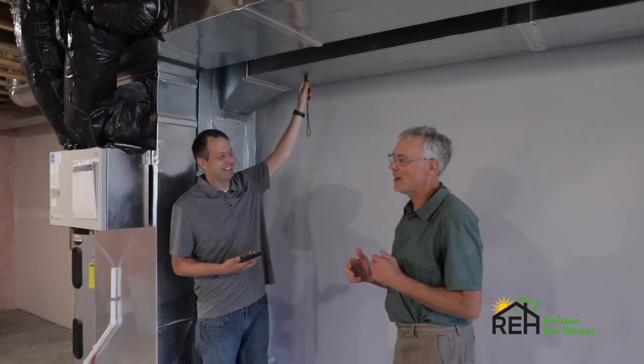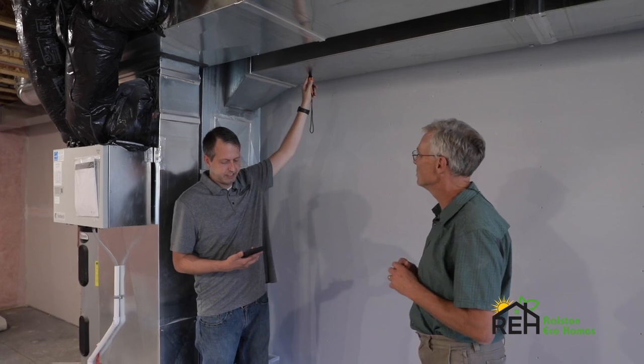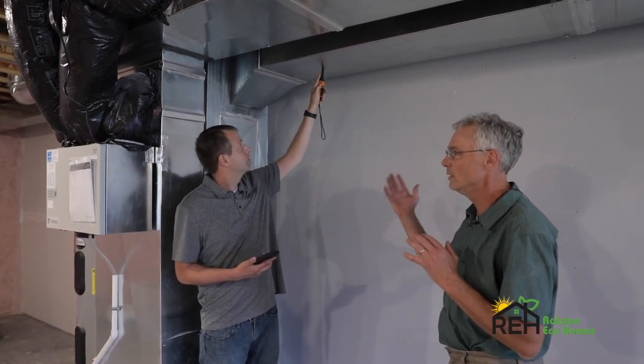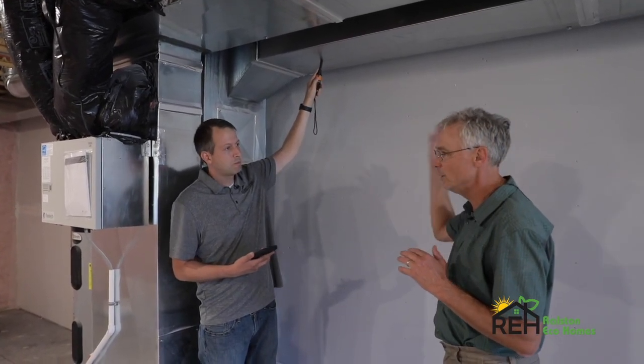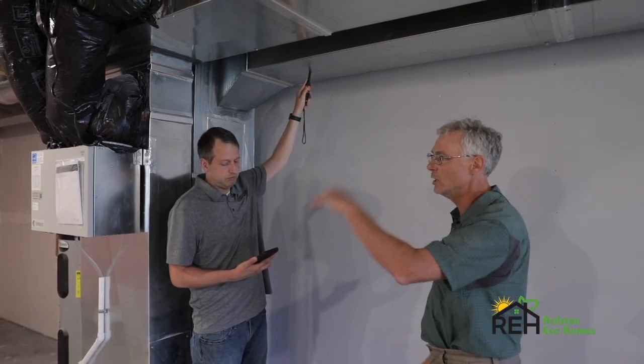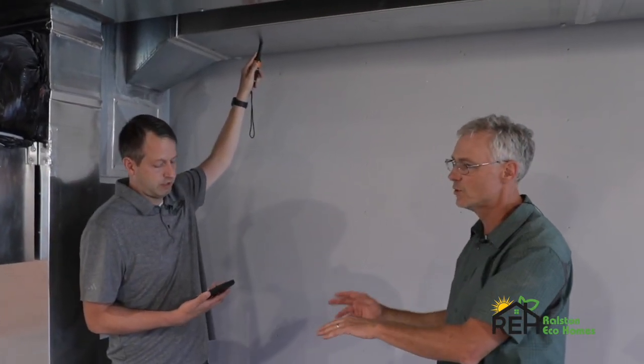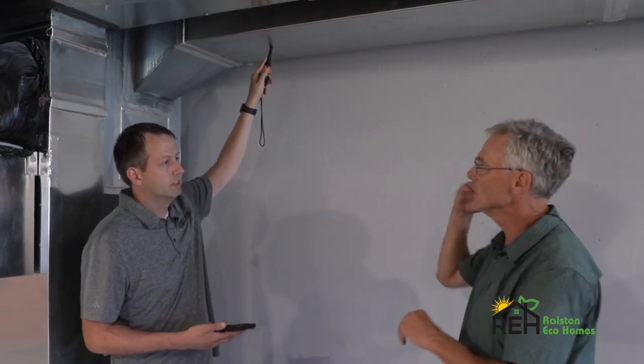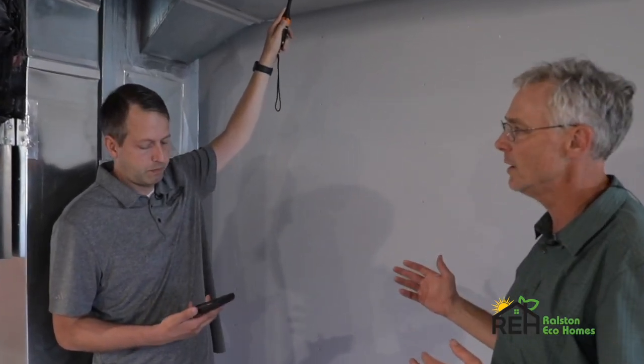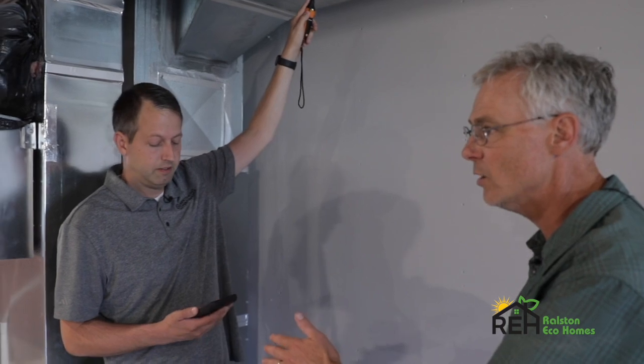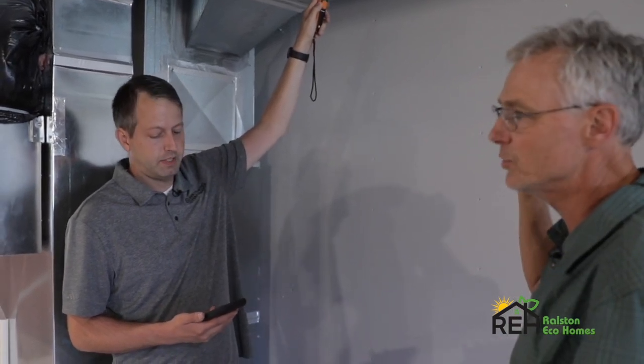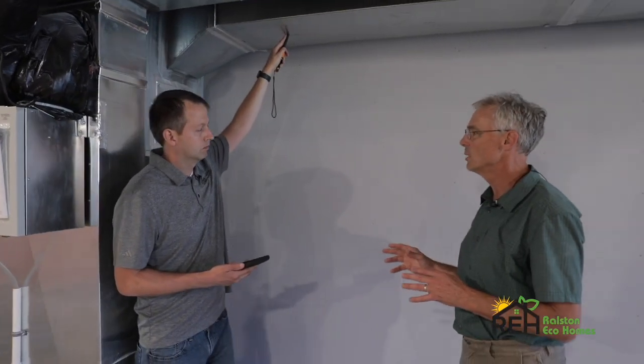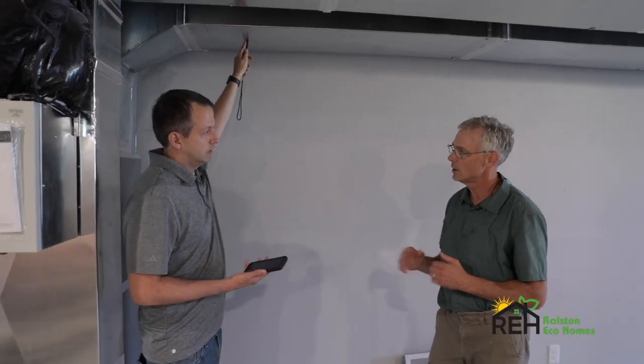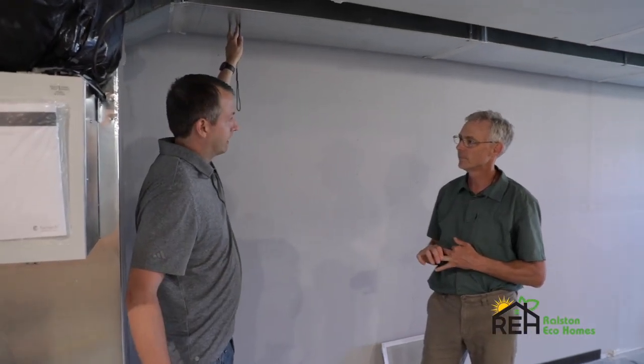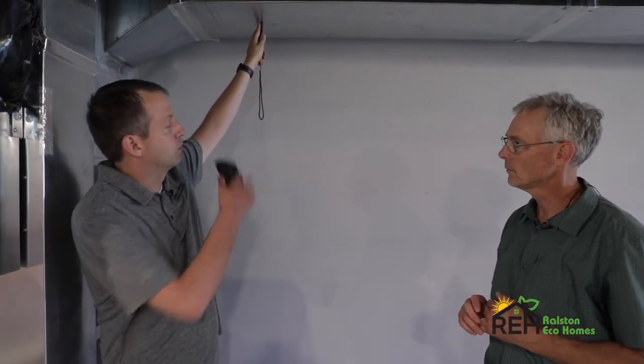That's correct. Adam, again, I'm not an expert at these kinds of things, but it's hot outside right now, so we're delivering cold air to the house, and then we're returning warmer air to the system so that it can cool it and then send it back. And so there's going to be a differential in air temperature between the return air and the air that's going out to the house. And on a system that's working properly, the differential in those temperatures is what? It should be anywhere from like 18 to 20 degrees. 18 to 20 Fahrenheit. Yep, from what's coming into the return and what's coming out of the supply side.